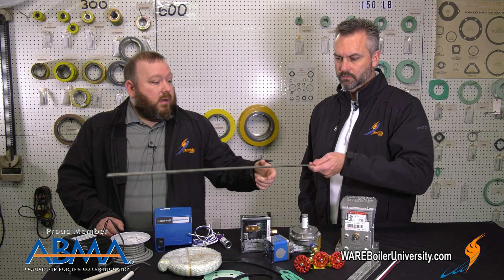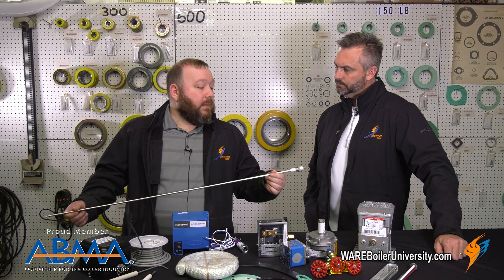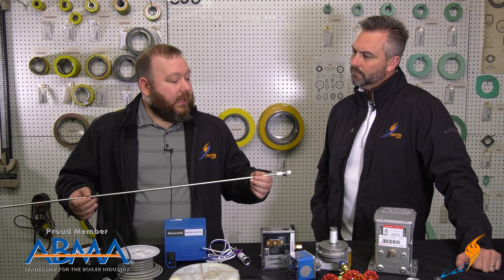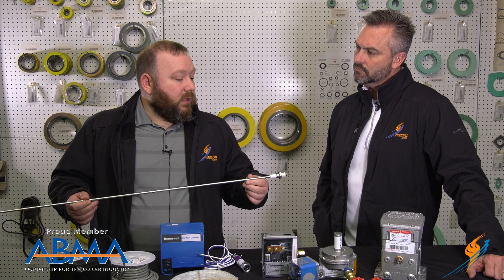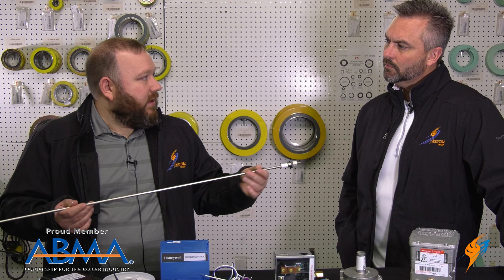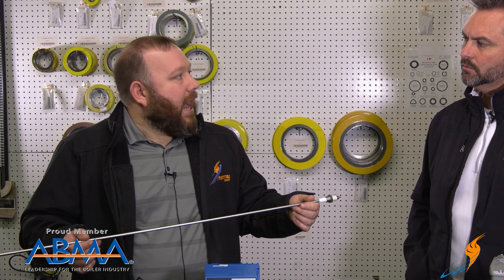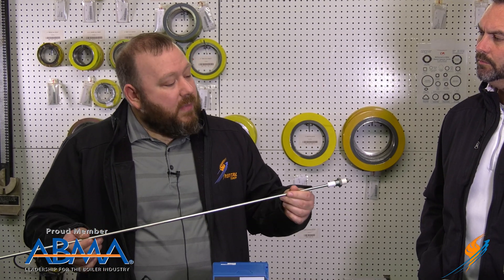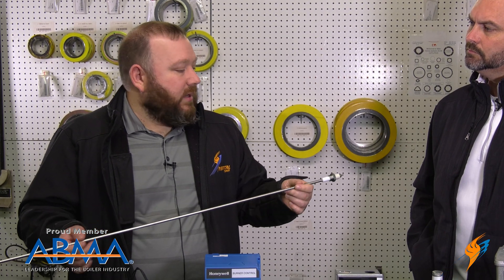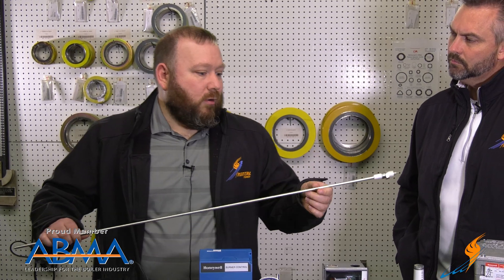Some boilers have probe-type low water cutoffs or high alarms, so you might want a spare probe or gasket for when you need to change those out. Just like your igniters, these things can get sooted up and crudded up, and you need to make sure they're clean and giving accurate readings. You may take these out from time to time, take some sandpaper to them, but they're very inexpensive so you might as well have a couple sitting around.